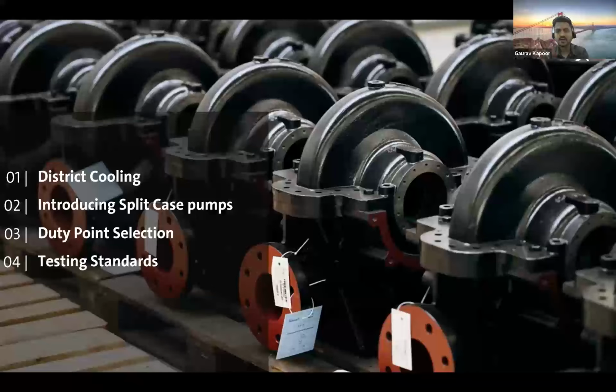This is very important to understand: if you are going to buy or use a split case pump in DCS, how you should look at the pump curves, and what the duty point selection should be. We'll end today's presentation by briefly understanding what testing standards are associated with these pumps, because when you are going to procure these machines, you should also understand what type of testing or test certificates you should request from the manufacturers to make sure whatever you need in the project is being delivered. Because DCS is all about efficiency and sustainability. So if any efficiency standards are being committed, they should also be delivered at site. Which is also very important for CAPEX and OPEX calculations, which are done before any district cooling plant is designed or established in any municipality or district town.